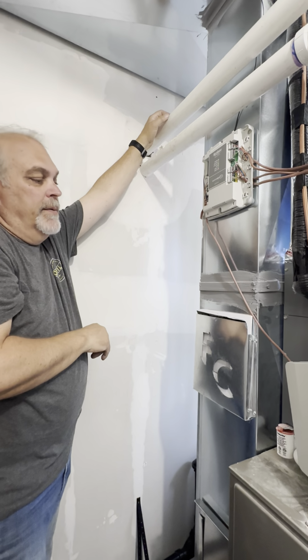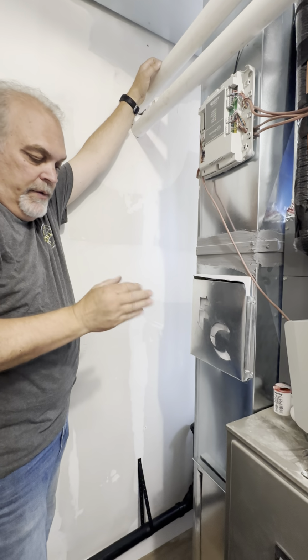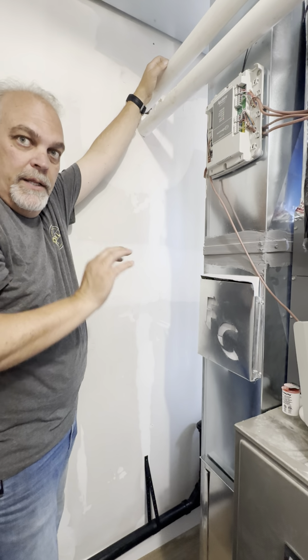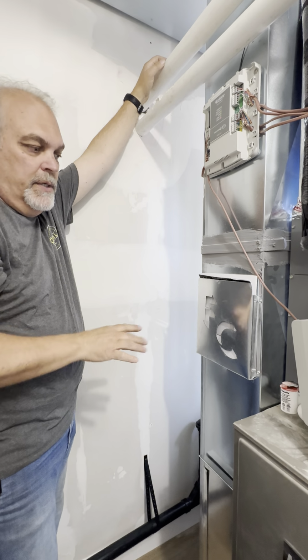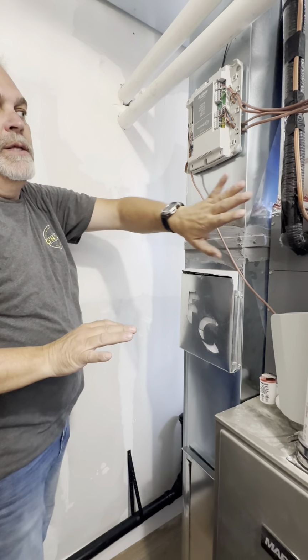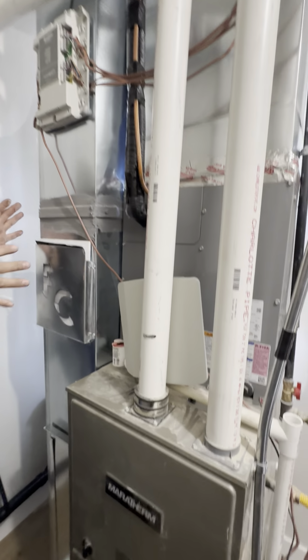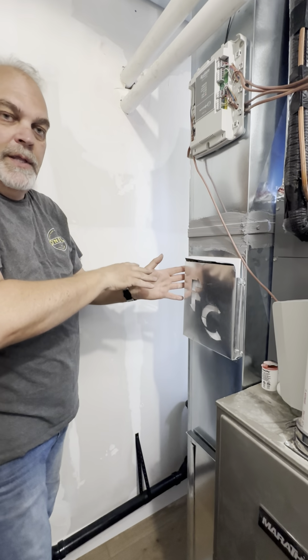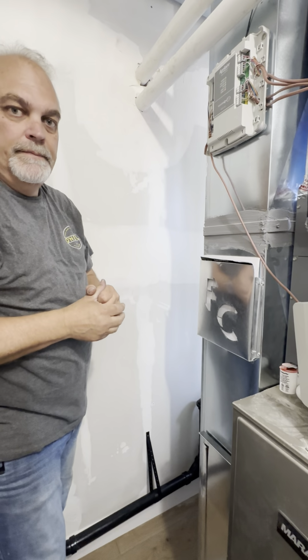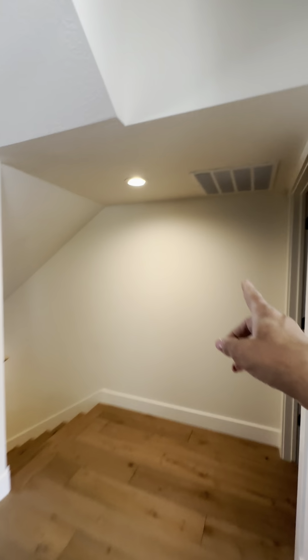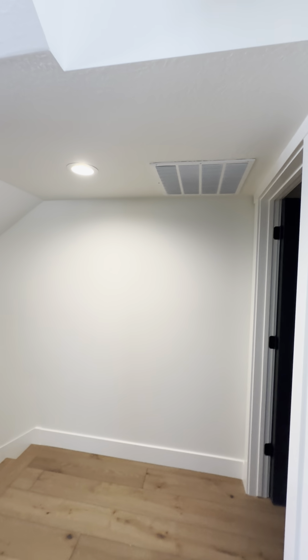And we've done that before and had really good luck cutting a lot of the sound down, just creating space. This cannot be done in the supply side, but in the return air side, we can do this type of thing and still maintain good airflow. Yeah, and that will help with the noise that's coming out of the vent here, obviously the return air vent. So, and it should help with the upstairs one as well.